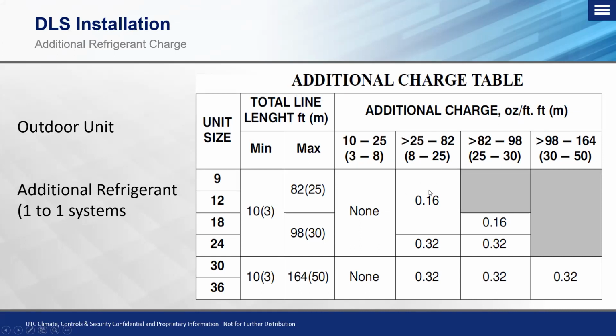Okay, typically on these systems, you're really not going to be adding much more than a couple ounces at most to the system, not a couple pounds. And of course, if you have any questions on this or you're running into any issues, you can always call me. I have software where you can give me total line set lengths and I can just spit out an additional charge for you. But I always tell guys, it's really important to learn the basics, just in case I'm not available to get a hold of, that you have the ability to calculate your additional charge.